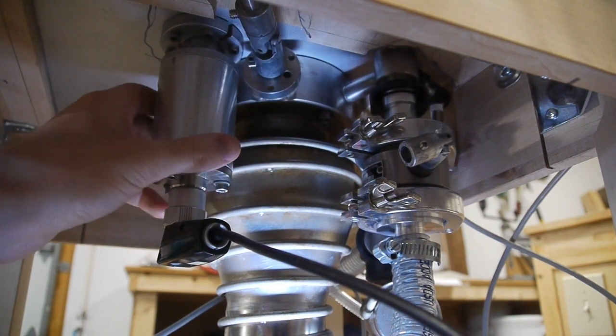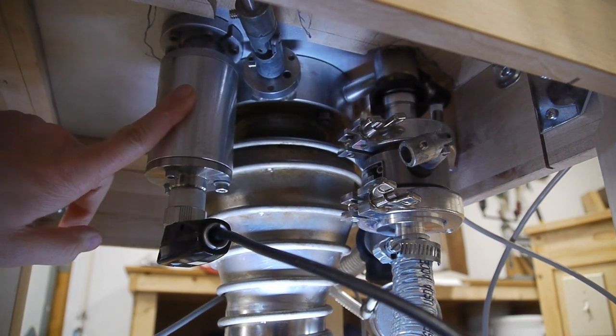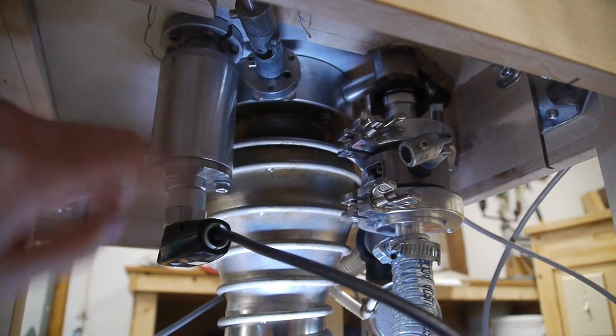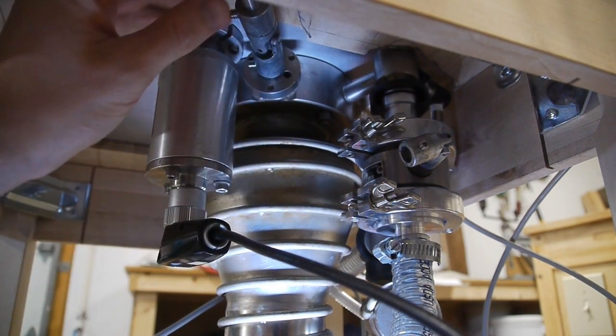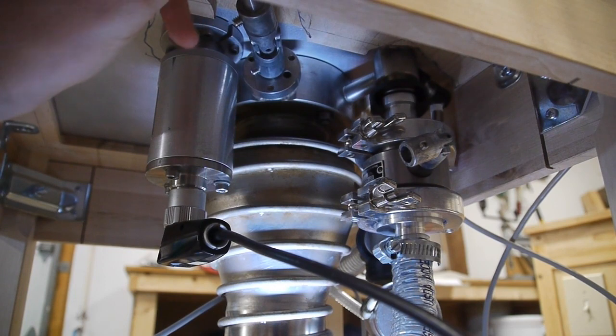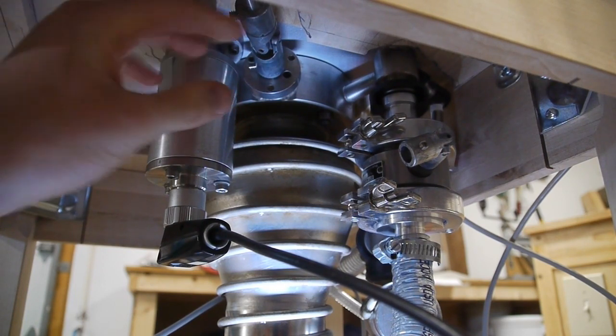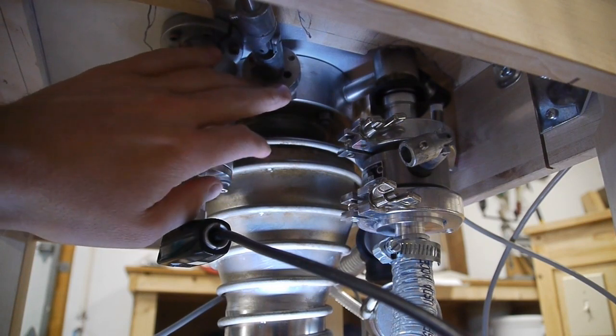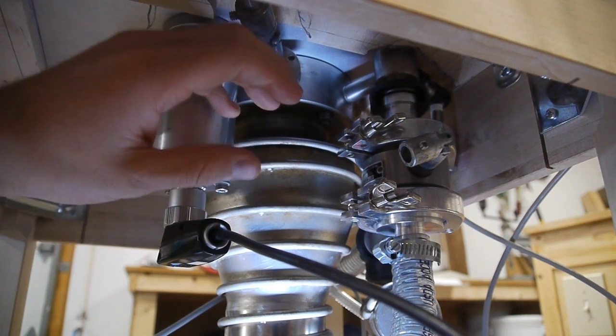We're looking at the underside of the vacuum table. This is the high vacuum penning gauge and this is the diffusion pump. This joint here is a universal joint that's connected to a shaft that goes outside the cabinet so that I can open and close the valve that it's actuating on the top of the diffusion pump.